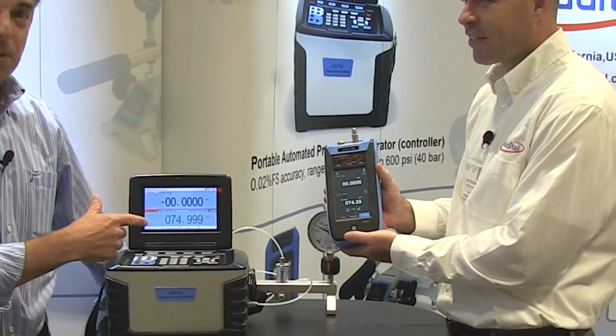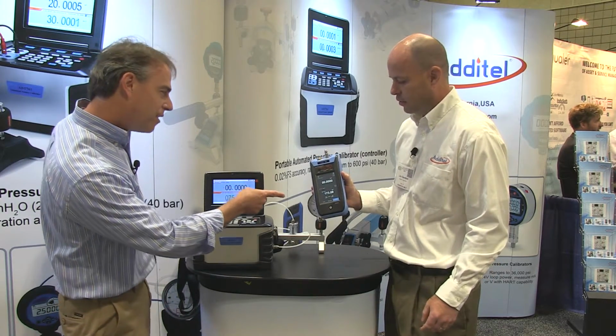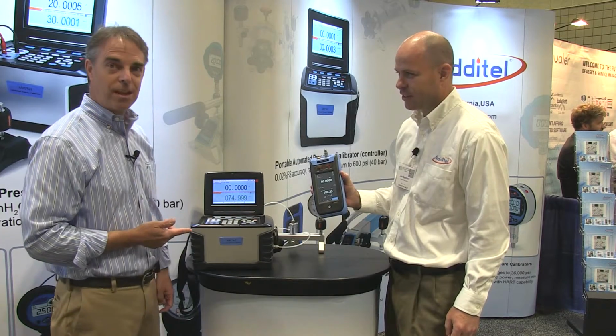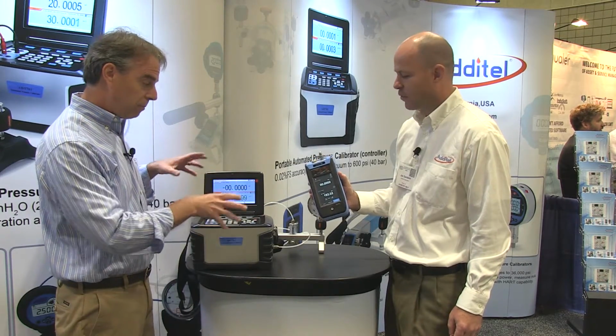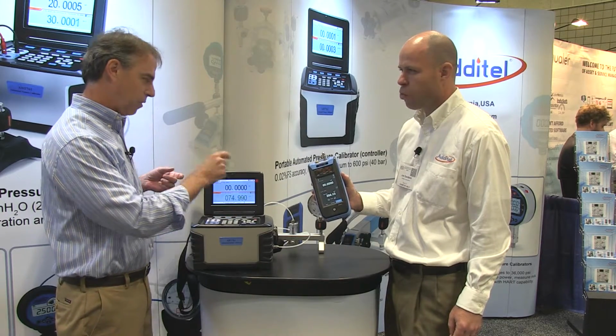So both of these units, by the way, are actually controlling pressure. This one is sitting at 75 PSI and has been for about 15 minutes. This unit is going up to 300 PSI in the palm of your hand. Automatic control, similar function set, I would say, generally to this unit. It's got an electrical module on it, pressure control, pressure measurement, but less than 5 pounds, right? Or 4 pounds, that's right. Yeah, a little weight. Less than 4 pounds. And so the portability aspect is obviously something that's very attractive.